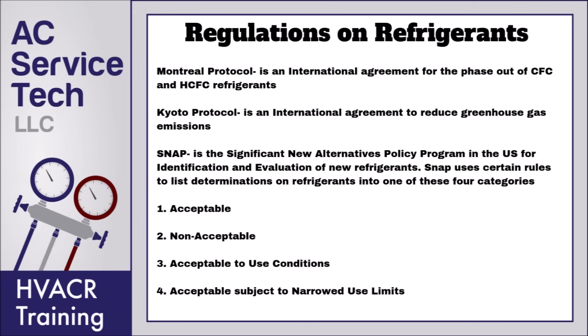SNAP was a Significant New Alternatives Policy program in the United States for identification and evaluation of new refrigerants. SNAP uses certain rules to list determinations on refrigerants into one of four categories: acceptable, non-acceptable, acceptable to use with conditions, and acceptable subject to narrowed use limits.